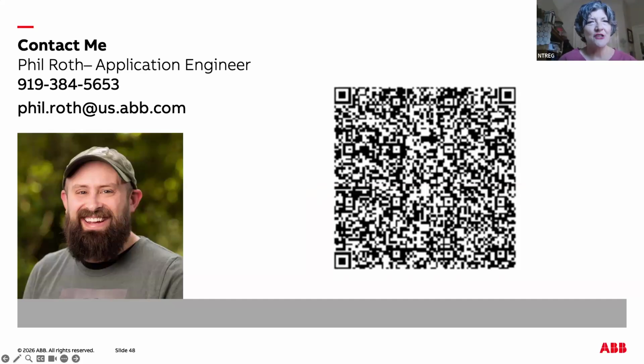For those of us that are not engineers, could you tell us what a meter socket adapter is? Yeah. So if you're familiar with a traditional automatic transfer switch, it is what it sounds like. It automatically transfers anytime the grid goes out from your primary source, the utility, to your backup source, the generator or energy storage system. A meter socket adapter is like an automatic transfer switch, except it sits in between your meter socket enclosure and your utility meter. So it creates a sandwich, so to speak, between the gray box on the wall and the meter that sticks off of it.